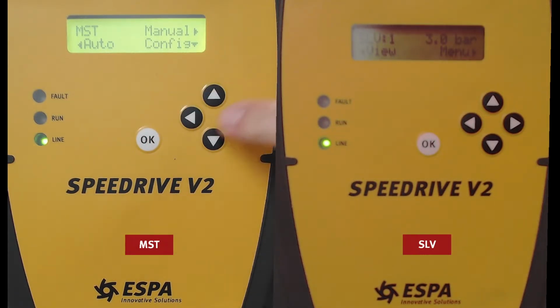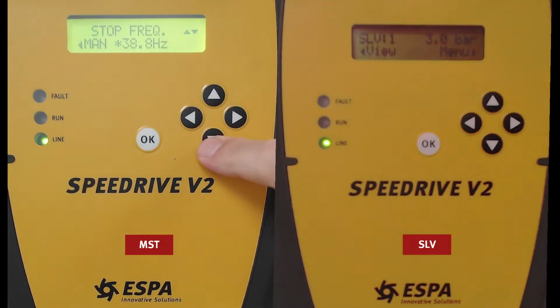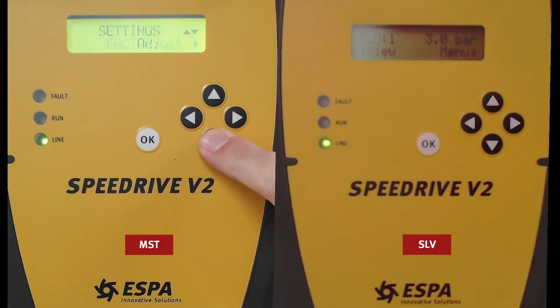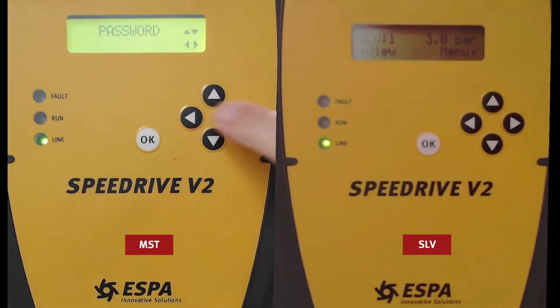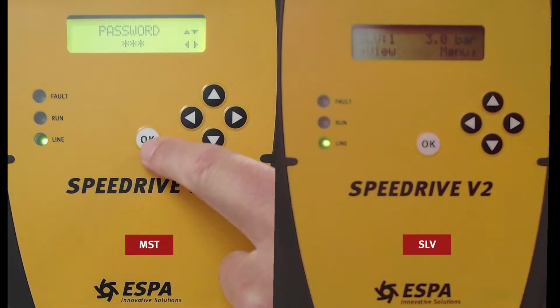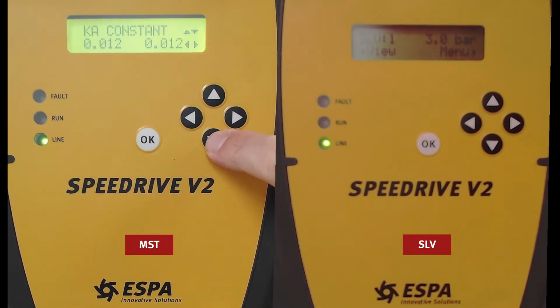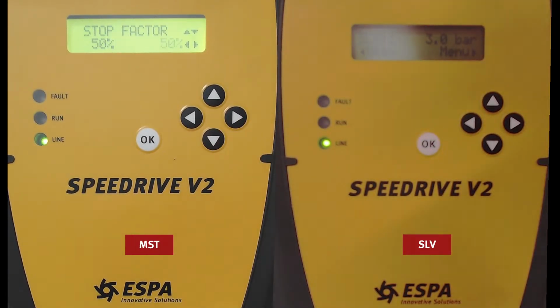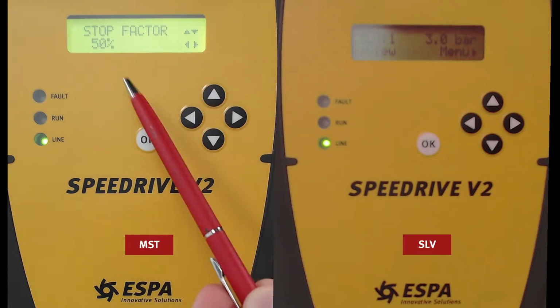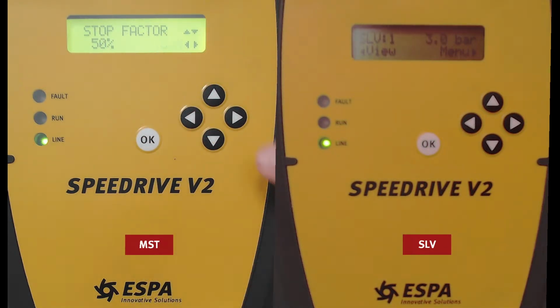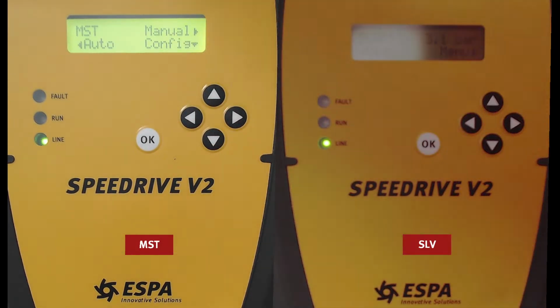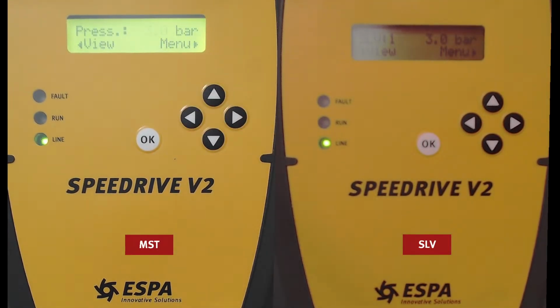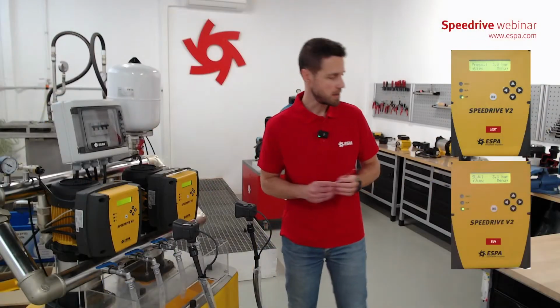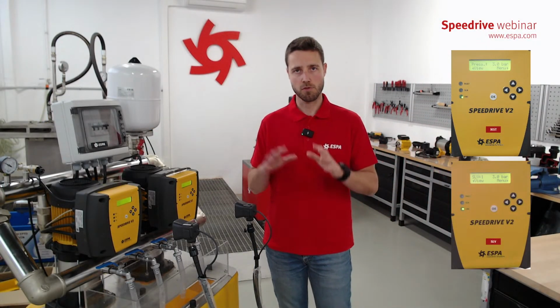So we can leave it now to configure. If you remember, we will go again to the advanced settings. Okay, 3 times right. Okay, constants. And the stop factor is set at 50%. If it doesn't stop when it's running dry, we have to increase it 5% by 5%. Okay, and go back. Auto mode. So until here, I think that's everything for the startup.